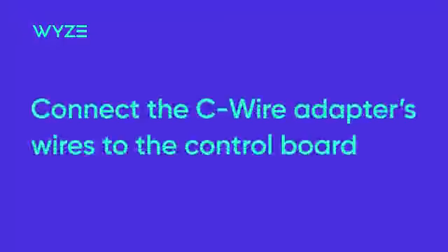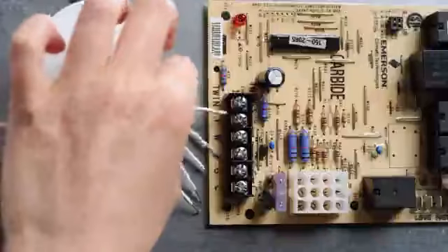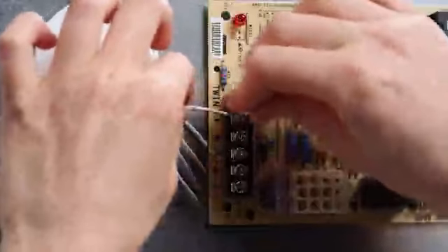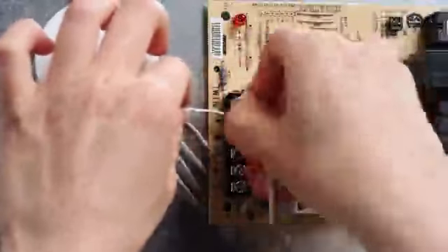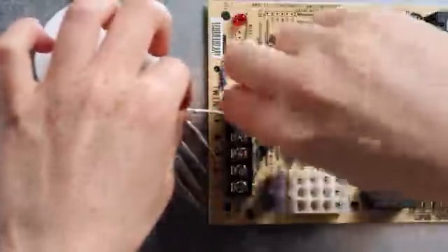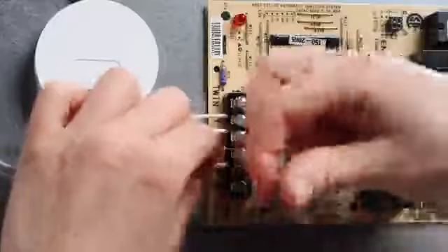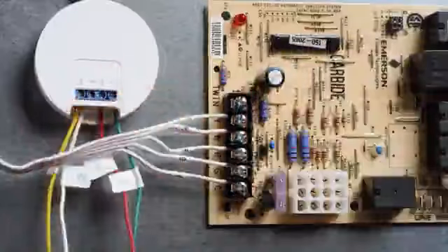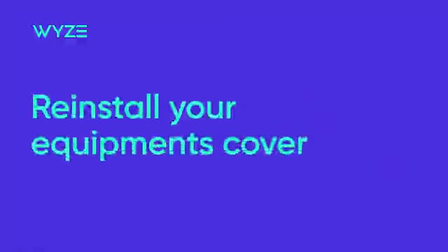Now we're going to connect the C-wire adapter to your control board. The C-wire adapter has 5 wires labeled Y, W, R, G, and C. Connect each wire to the matching terminal on your control board and then tighten the screws to ensure the wires are securely connected. Replace the cover on your HVAC system. It is important to ensure the cover is securely locked into place, as some HVAC systems have a switch that will prevent the system from turning on if the cover is not correctly in place.